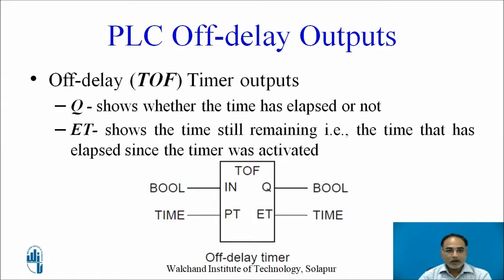Q shows the output — whether the time has elapsed or not. ET, elapsed time, shows the time that has elapsed since the timer was activated. The data type associated with Q is boolean, meaning either 0 or 1, whereas the data type associated with ET is time, meaning the value is expressed in seconds.